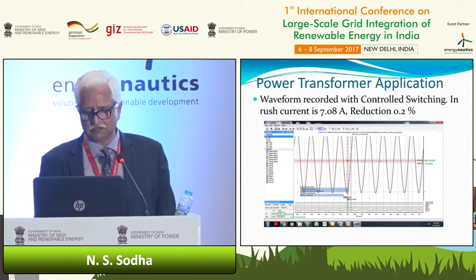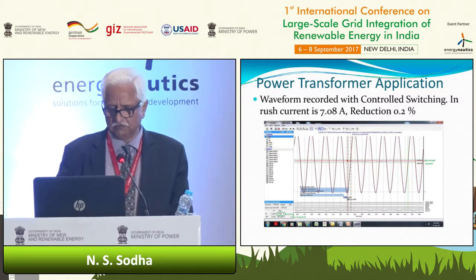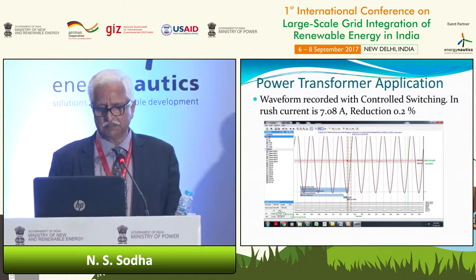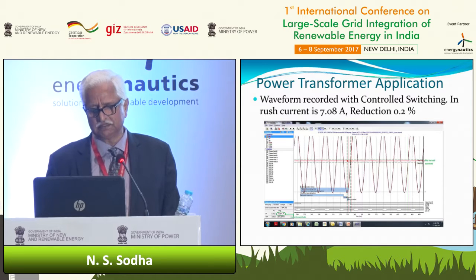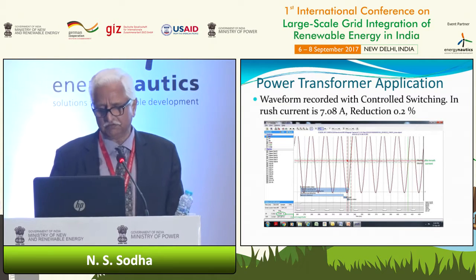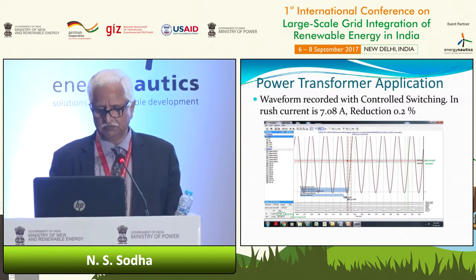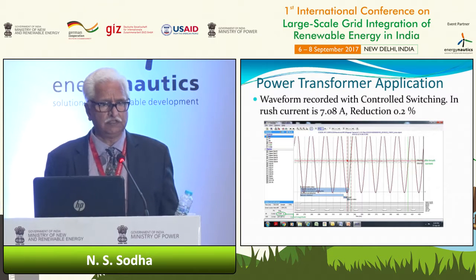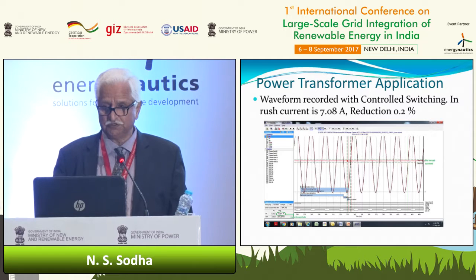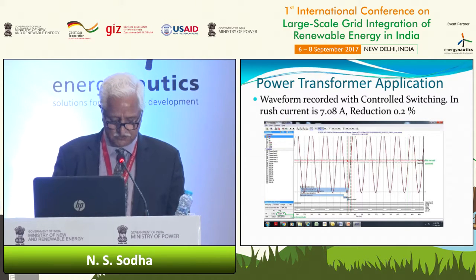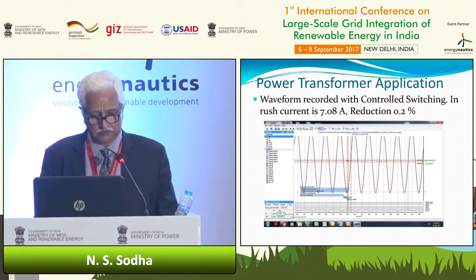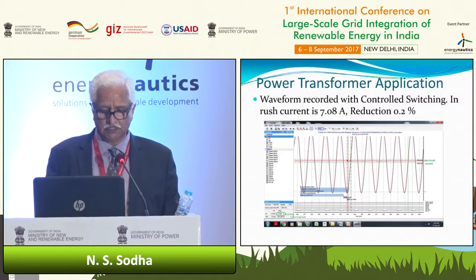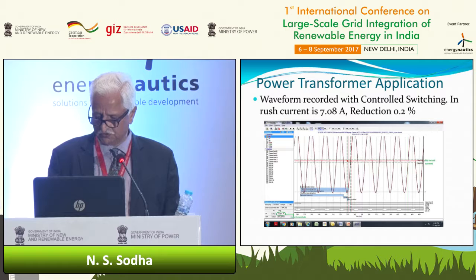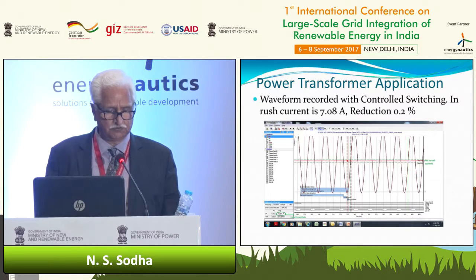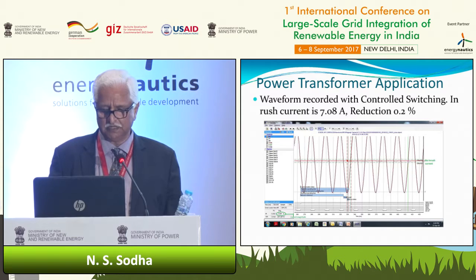Now when the control switching was applied on the transformer, the waveform has improved and the control switching inrush current has come down to 7.08 ampere, and definitely it has improved the situation. So let me tell you that the transformers are basically the major cost in the transmission equipment, and if the transformer fails, it's a major, direct loss to the utility, and if the outage is a long outage, then it is going to cause system availability issues also. So we need to see that the primary equipments are properly protected, and control switching definitely helps in that.